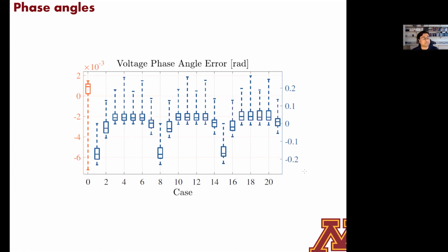Okay, I'm going to show you two results. There's a paper that has many more. Here is the result that shows you the error in the voltage phase angle. And you can immediately appreciate that no matter which version of the single slack power flow you were solving, we get an order of magnitude improvement with this distributed slack. So it's definitely much more aligned with what happens in real time when you simulate all the dynamics of the generators, when you respect all the operational aspects that are going on behind the scenes with respect to the power system. And you can definitely appreciate that orders of magnitude improvement that you get when you solve the problem. And I must tell you that it takes no additional computational burden. It's just acknowledging what's happening behind the scenes in specifying those generator outputs, right?